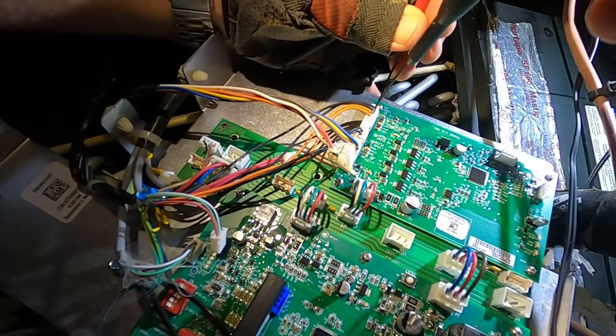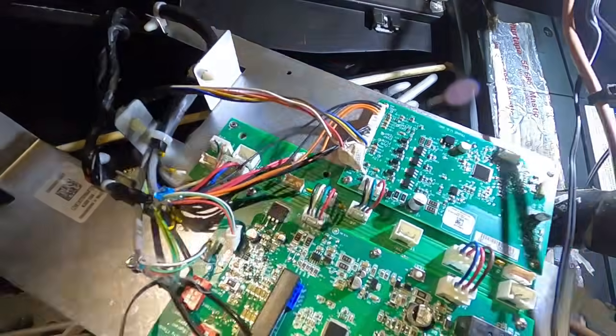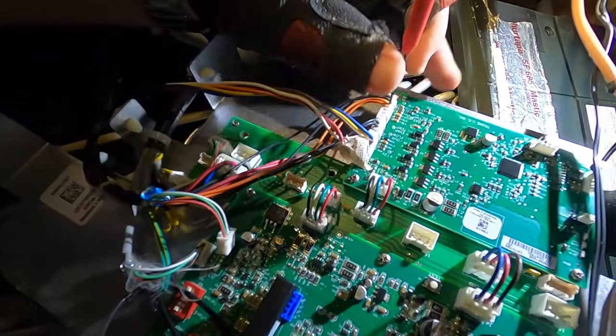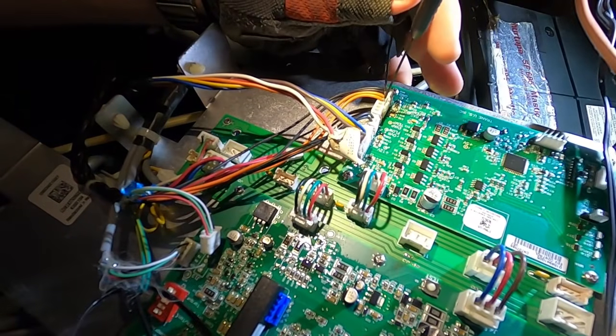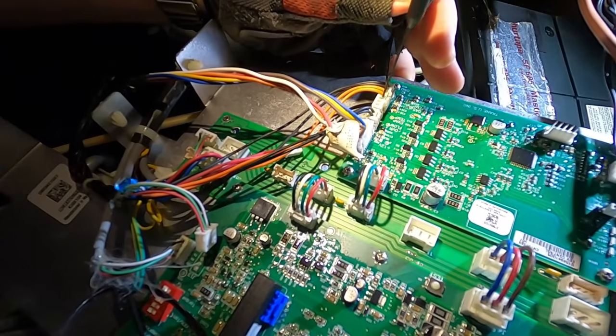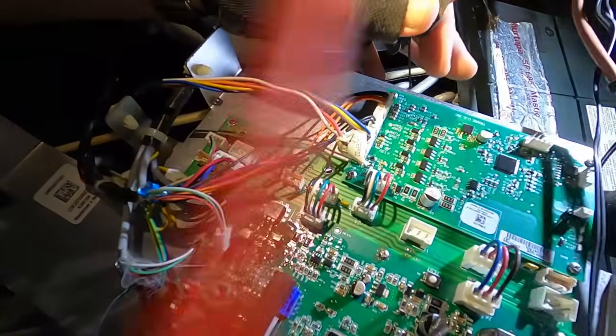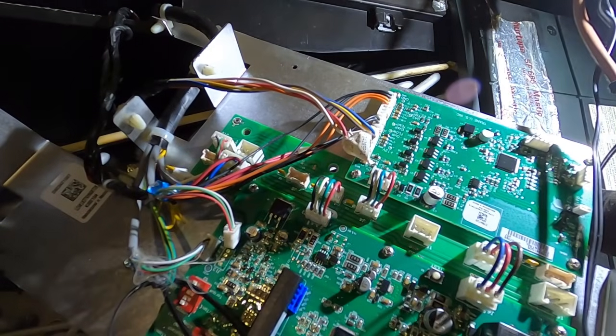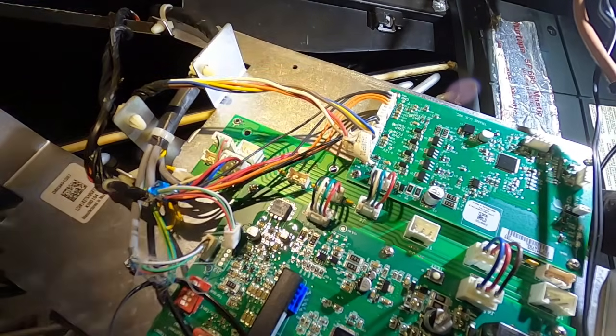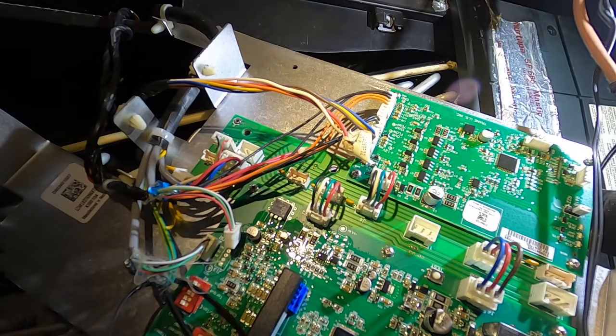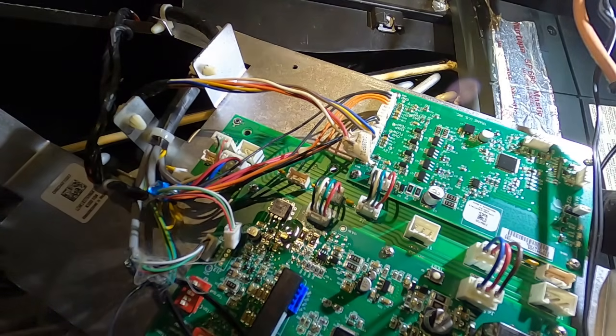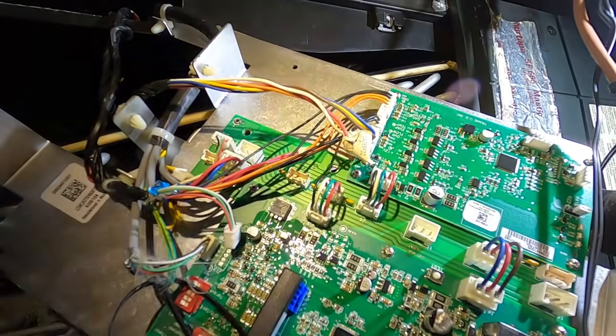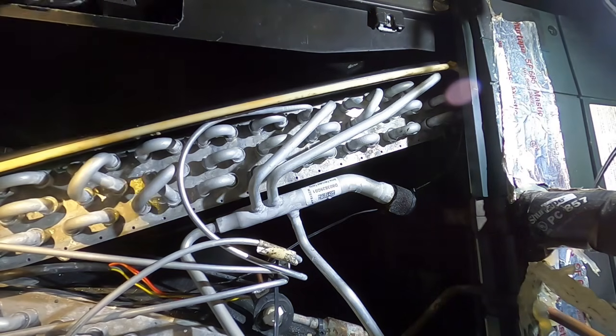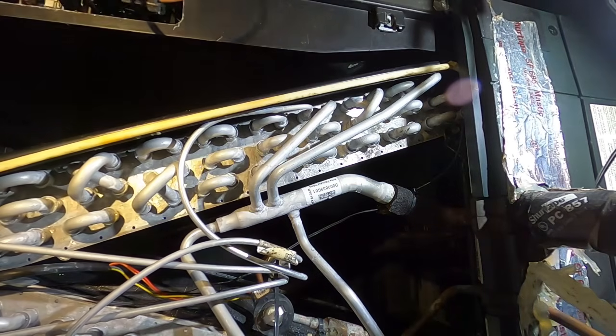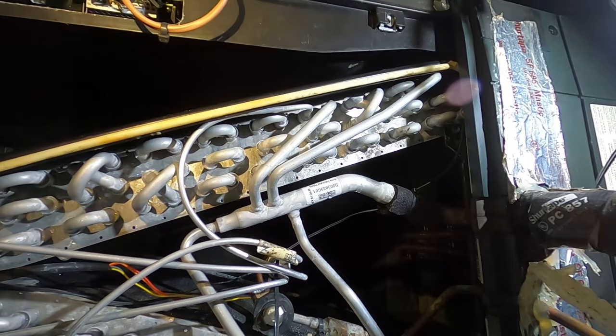I wish these needle probes were a little more rigid. You try to get them pushed down in there, and they want to kind of bend on you. And I got 1.6 right there. So both of these sensors are reading 1.6. 1.6 is typically going to be in that 70-ish to 74 degree range, 69, somewhere in there. I know it's right. I've seen it 1,000 times of testing these things. So those sensors are reading the right temperature.